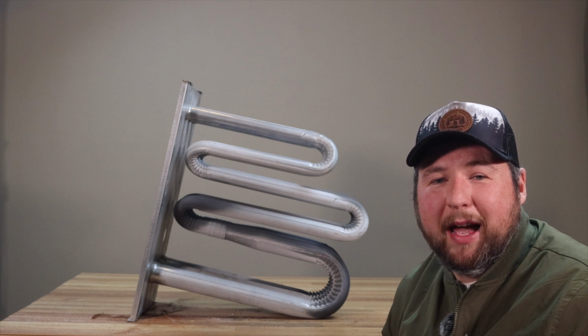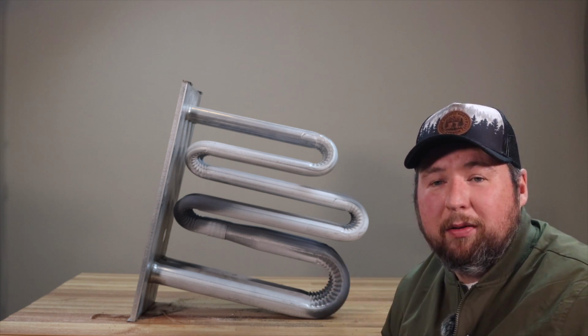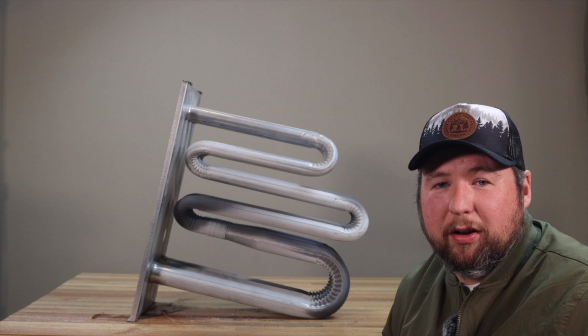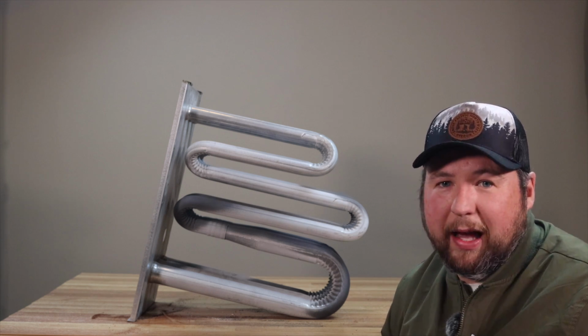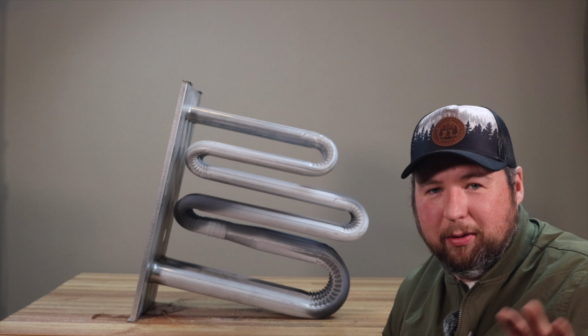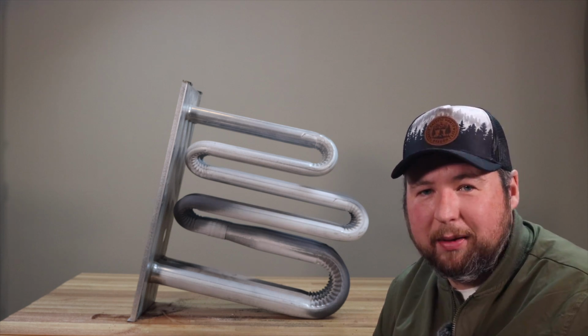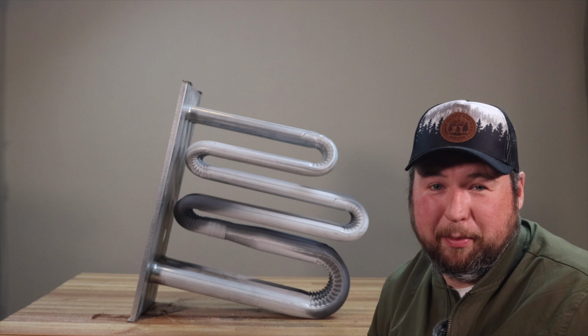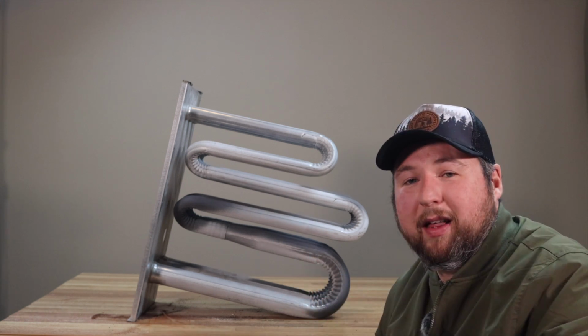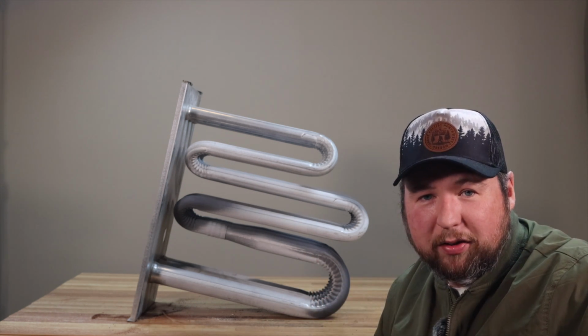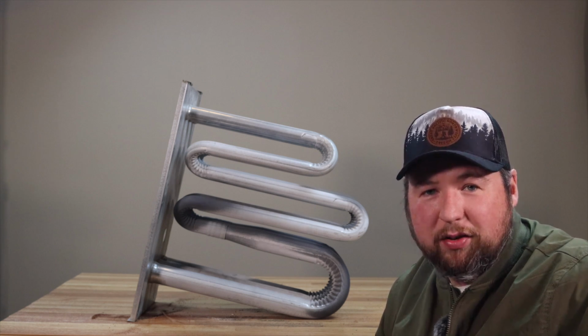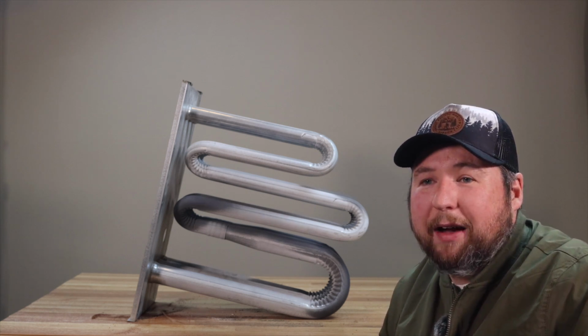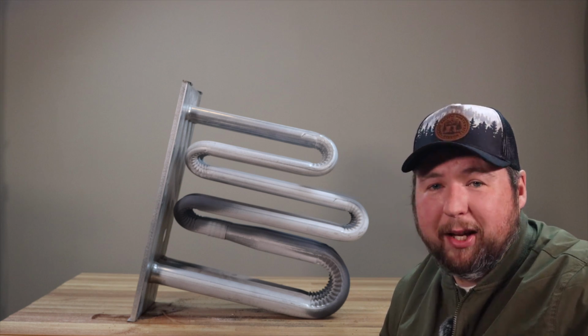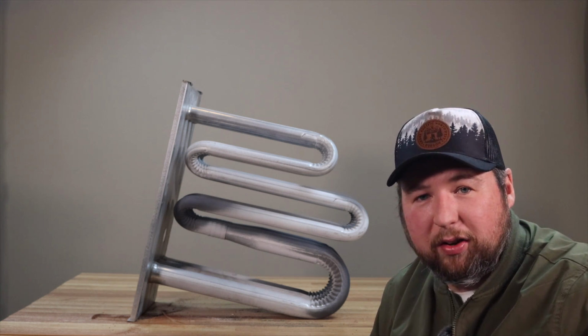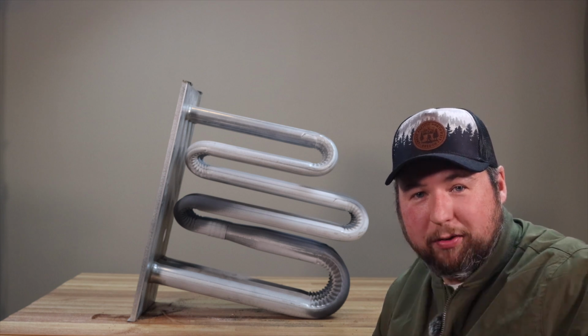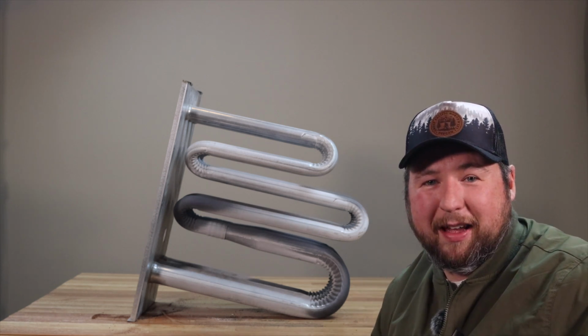So who tells us that we have to change our heat exchanger? Here in the US, we have the American Gas Association. They're pretty much the ones who approve all the gas-fired appliances and make sure it all meets the standards. Well, one of them anyway, because there's a bunch of them here in the US. Basically they say if you have a compromised heat exchanger, you have to change the heat exchanger or the entire furnace. You don't have to change the whole furnace. If you can get a replacement heat exchanger, it's perfectly fine to change just the heat exchanger. So you sales guys, don't be pressuring people to replace it just because they have a tiny little crack.